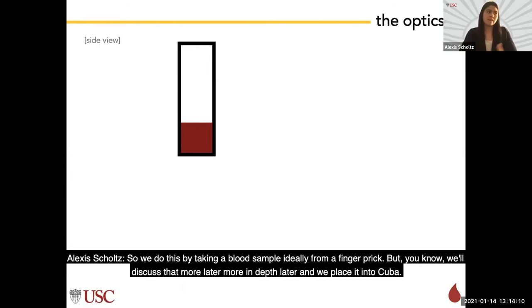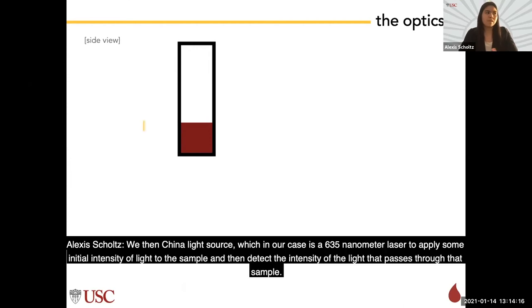We do this by taking a blood sample, ideally from a finger prick, and we place it in a cuvette. We then shine a light source, which in our case is a 635 nanometer laser, to apply some initial intensity of light to the sample, and then detect the intensity of the light that passes through that sample.